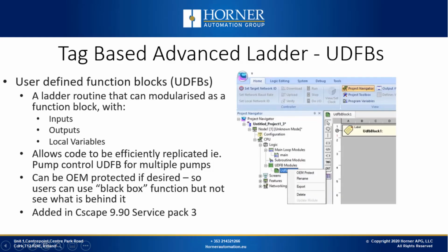For those of you who may have missed our earlier webinar on UDFBs, here's a brief overview. Another powerful tool unique to TagBased Ladder are user-defined function blocks. User-defined function blocks, or UDFBs, are ladder routines that can be modularized as a function block, where you assign inputs to the block and outputs to the block, and local variables used within the block. UDFBs allow your code to be efficiently replicated.